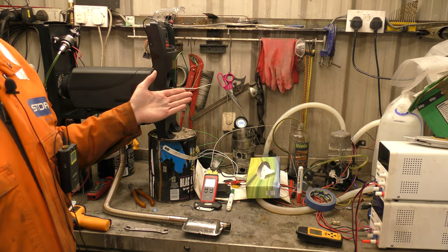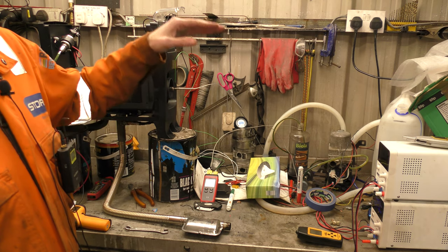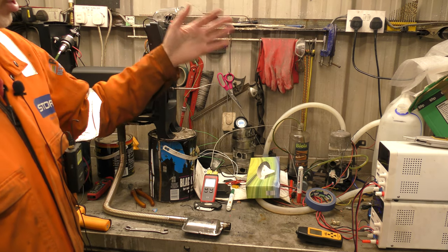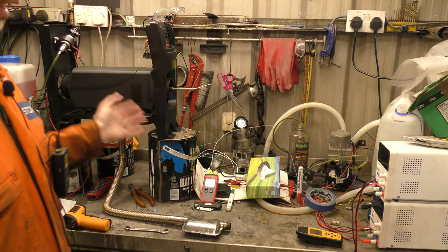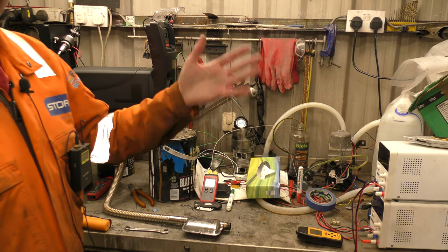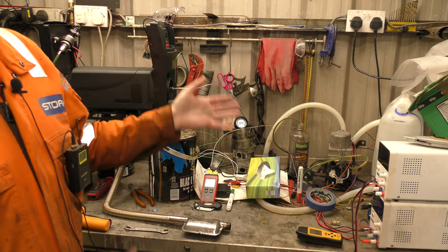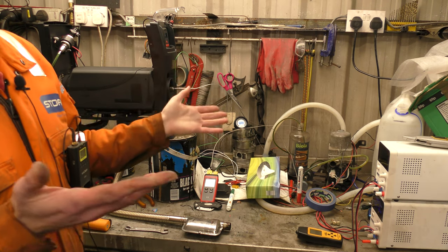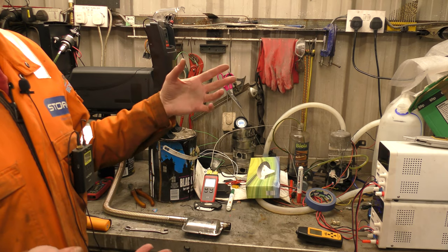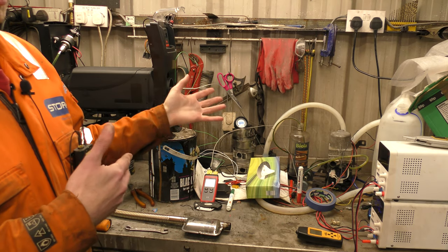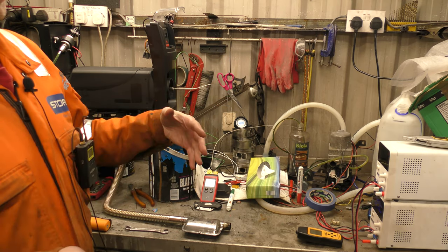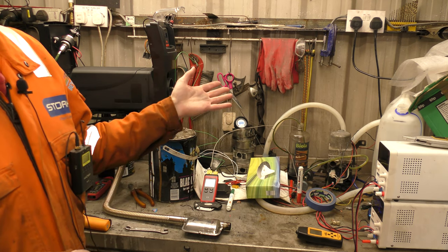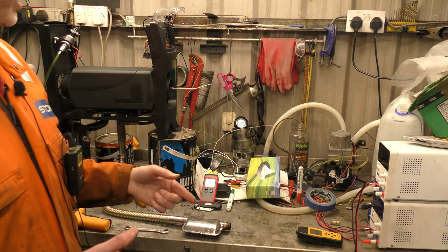So I'm going to start at my lowest fueling level of 1.6 hertz and then do 2.6, 3.6, 4.6, and then 5.5 because mine finishes at 5.5. We'll record all the data and then I'll make a graph and show the workings of air fuel ratios, what pump settings and fan settings get you, what temperatures, and how much carbon monoxide you get from said things.